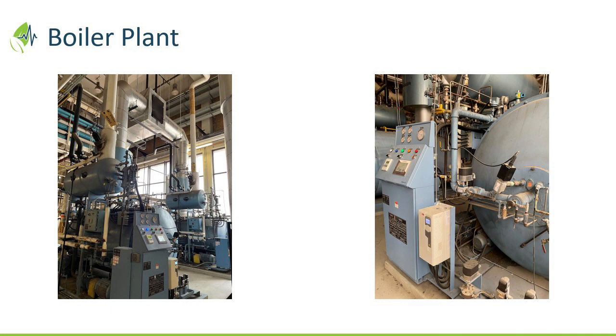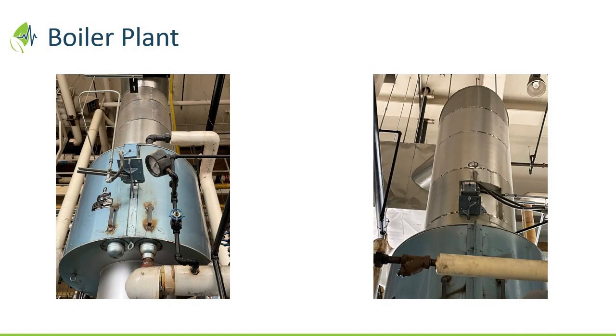The problem, I think, was that we used to run on oil in the winter times, so we were on interruptible fuel. We don't do that anymore. We decided maybe five or six years ago to go off interruption. That's where I think a lot of those problems happened, because the stacks would get full of soot and we had nothing but problems. And you found that the economizers were pretty fouled as well, right? I think you cleaned them up. Yes, we did. We spent quite a few dollars on that at one particular time. That's why we decided to go to uninterrupted fuel. That's actually a very interesting question. The government's looking at that as well, because interruptible fuel deals with that peak. If people won't use interruptible fuel, we need more gas pipes, and we don't want to be spending money on those right now.